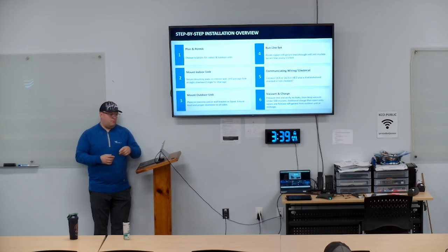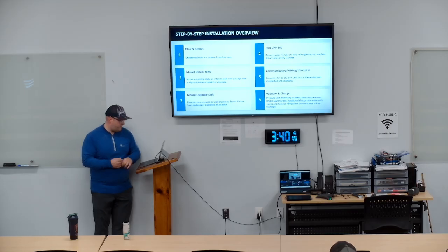Not that bad. But the manufacturer said, we want to be there when you do it, and it's not allowed to climb more than 12 microns in 4 hours. Because some of the manufacturers get crazy. He's like, yeah, you got to have a leak. And I'm like, you're nuts. Like, I've been told there's no way I'm going to be able to hold it. Sure enough, I found a leak. So if it keeps climbing and keeps climbing and keeps climbing, if it stops and it holds, then you're good. It may just be moisture in the system or something if it goes over 500. So suck it back down and verify it.